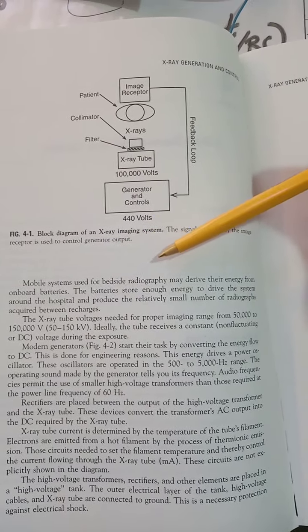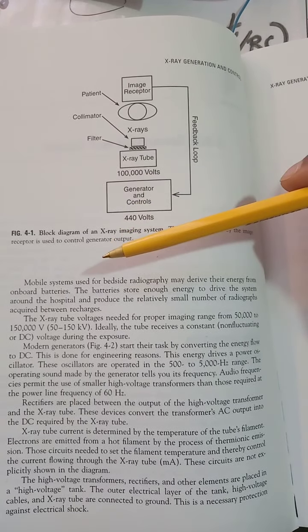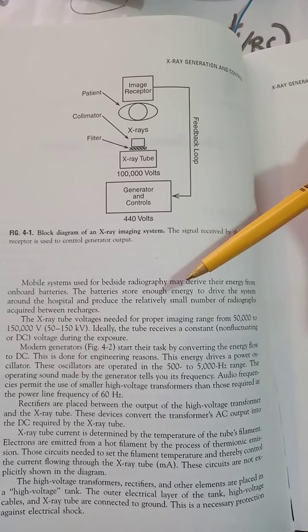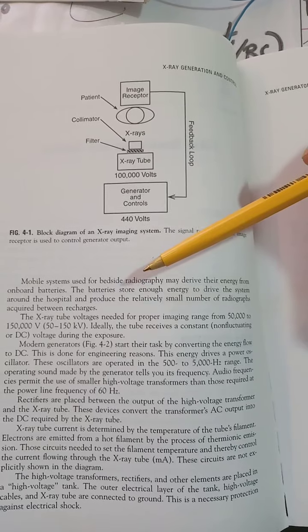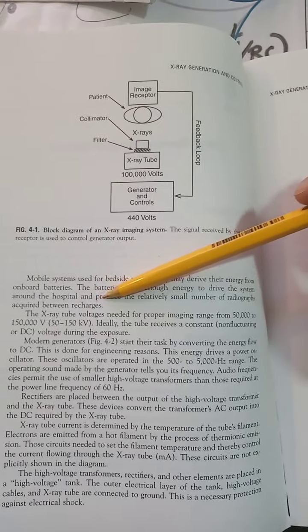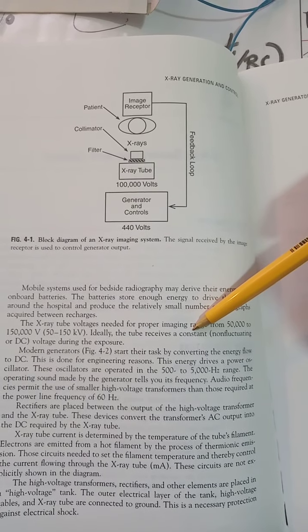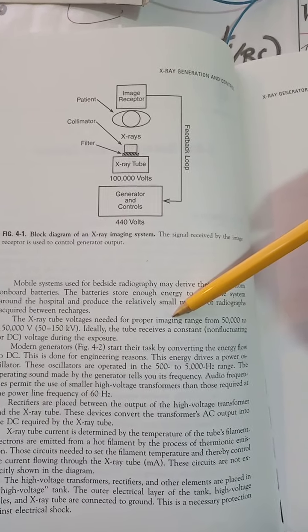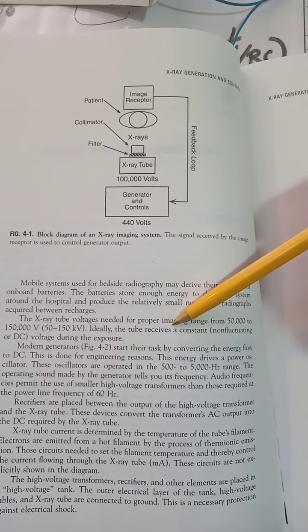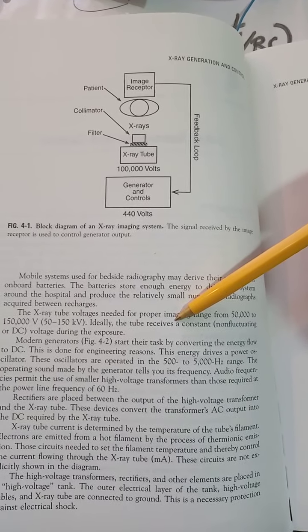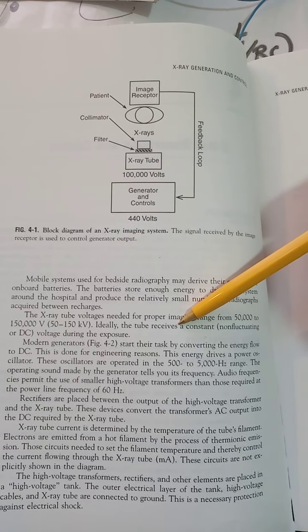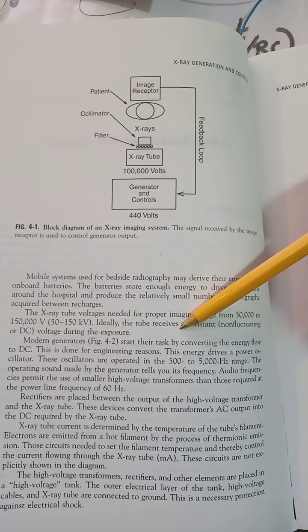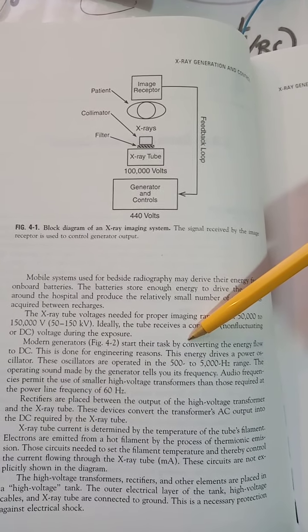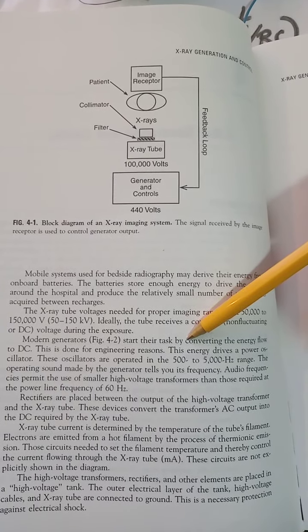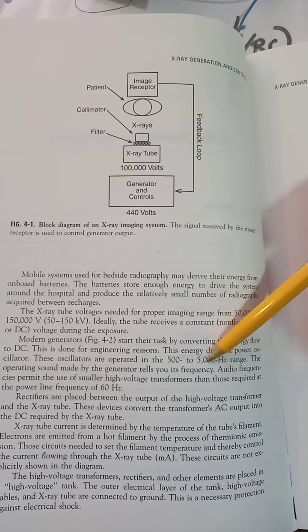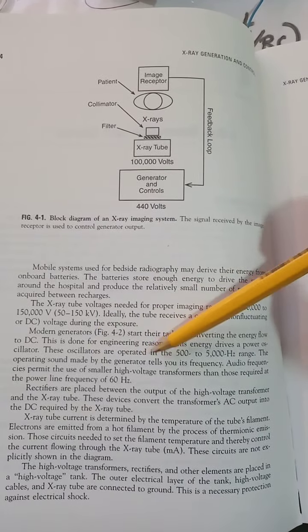So mobile systems are used for bedside radiography, and they derive the energy from onboard batteries. The batteries store enough energy to drive the system around the hospital and produce the relatively small number of radiographs required between recharges. The X-ray voltage needed for proper imaging is from 50,000 to 150,000 volts, ideally. The tube receives a constant, non-fluctuating voltage during the exposure. The modern generators start the task by converting the energy flow to DC. This is done for engineering reasons. This energy drives a power oscillator. These oscillators are operated in the 500 to 5000 hertz range, 0.5 to 5 kilohertz range, and the operating sound made by the generator tells you the frequency.